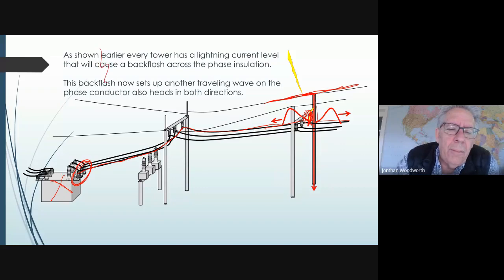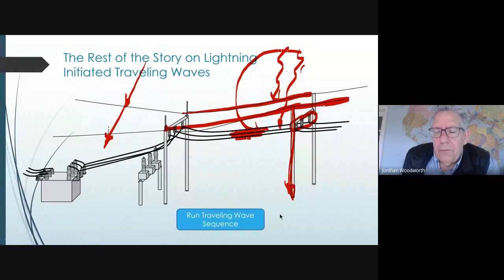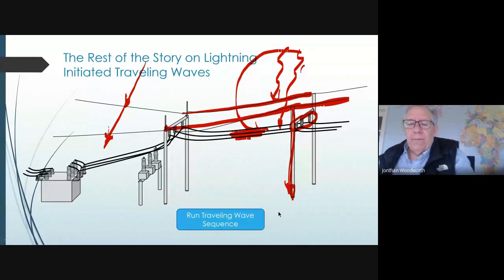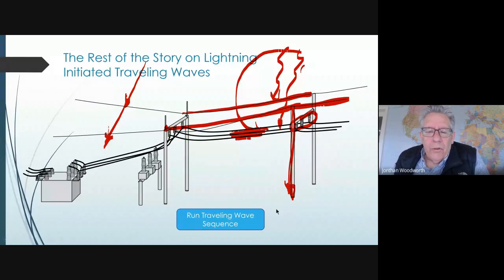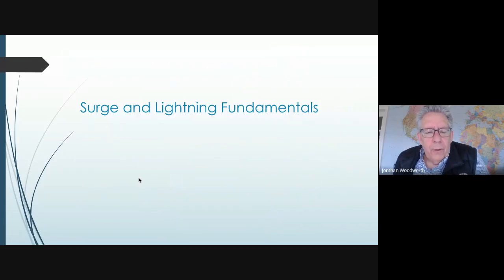It never gets in by a surge from the top or right through the top. It only gets in from a backflash, either a backflash or a direct flash to these phase conductors, and then they take it into the power system. Okay, so those are the 3 kinds of events that we try to take care of in power system protection. We protect the transformers, we protect the insulators, we protect other equipment in the substation from flashing over the insulators. The goal is to avoid this flashover. And the way we do that is with arrestors.